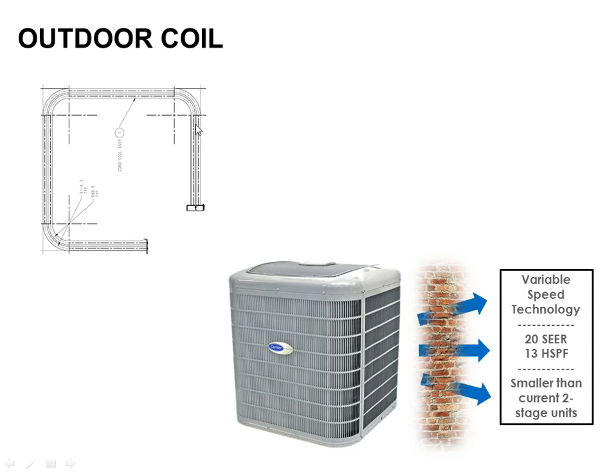Additionally, the coil is double rowed. So I don't know if you can see that on the drawing on the top left, but there's 2 rows of coil side by side. Somebody had asked me a couple weeks back if that's something you split to clean it in between, and it's actually not. It's 2 rows of coil sharing fins, so it's still like one giant coil, if you will. It's just double thick. So you cannot split it like I thought you could previously, but just mentioning that in case you happen to be on the call again.